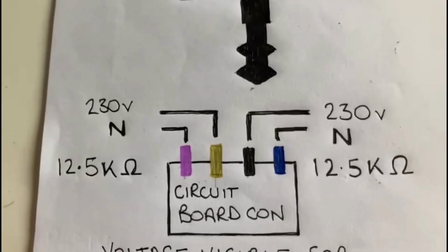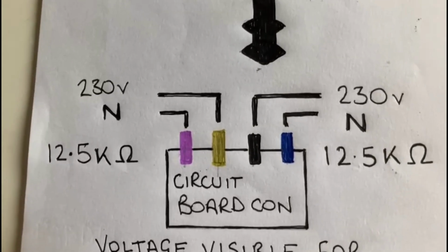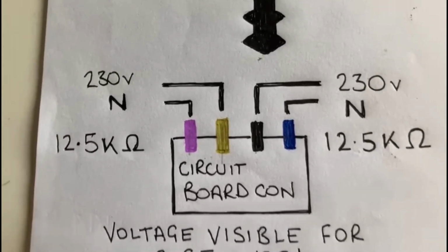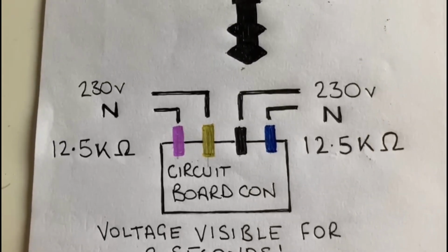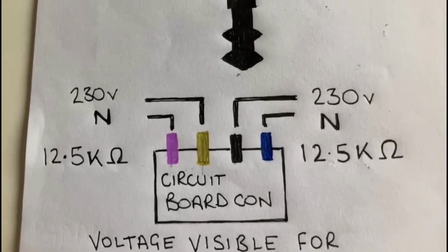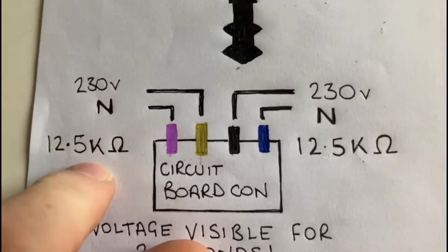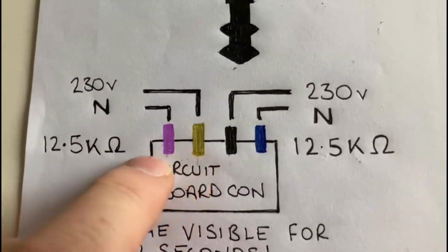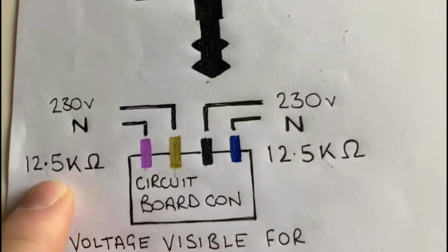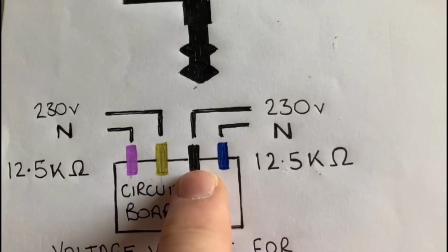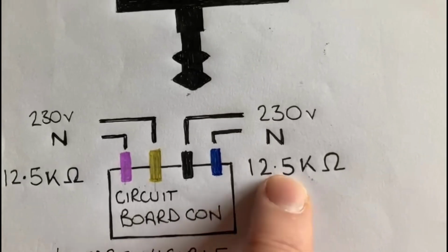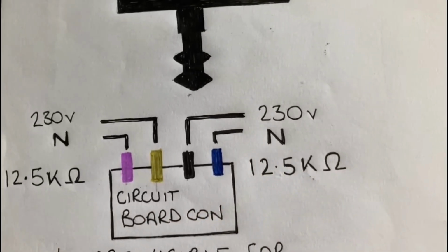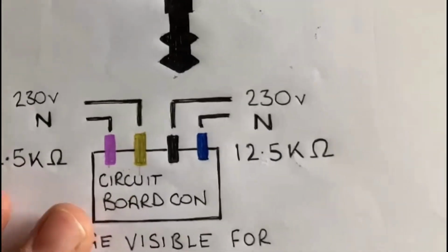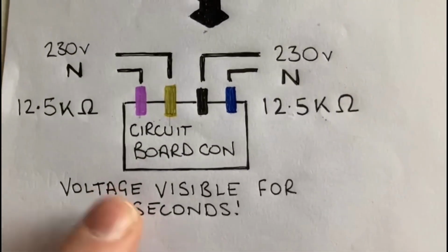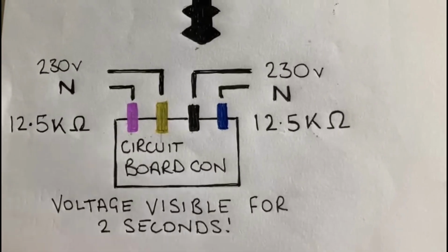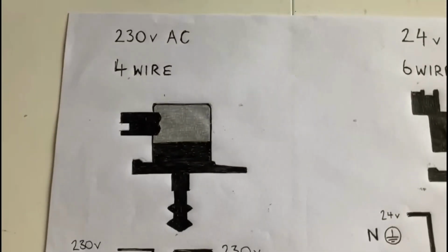But dead test the coils, so knock the power off, pull the fuse out, make sure you're working safely, do your safe isolation test, and then you want to be testing each coil. So between the purple and the brown you should get 12.5 kilo ohms, and between the black and the blue you should get 12.5 kilo ohms. So that's just to check your coils, and if you can get the voltage, it's only going to be there for 2 seconds. So they're the tests you can do on that motor.